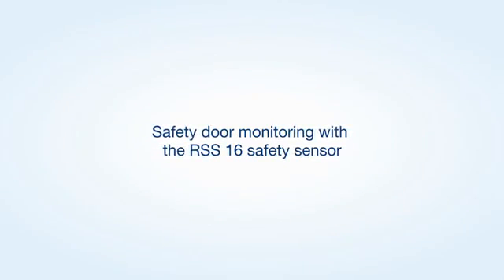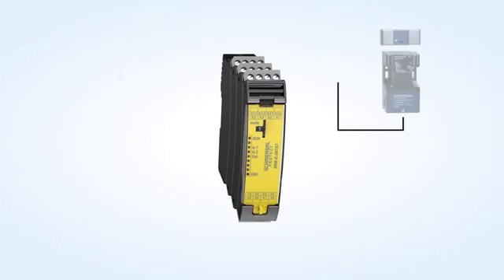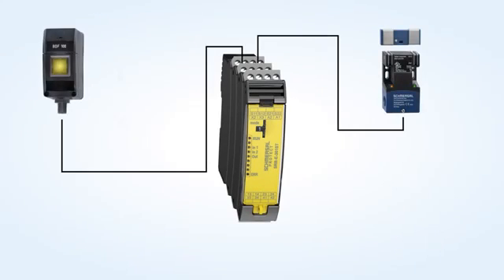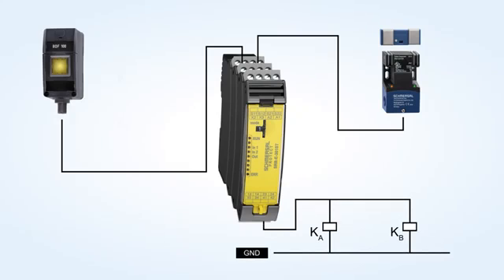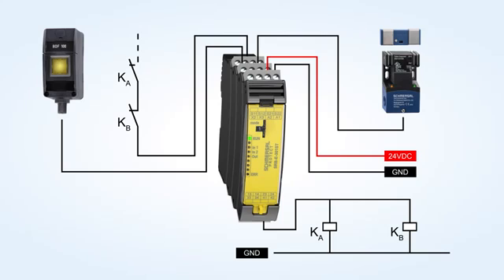Sample application of a safety door monitoring with the RSS 16 safety sensor from Schmersal and start button monitoring. The desired application can be simply configured by means of a rotary switch. Formerly saved configurations will be deleted first by turning the rotary switch to position C, configuration mode.